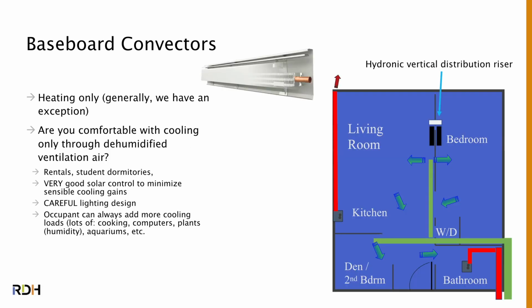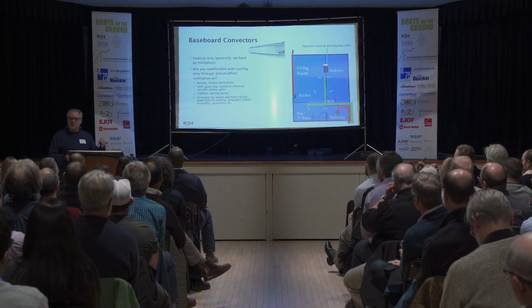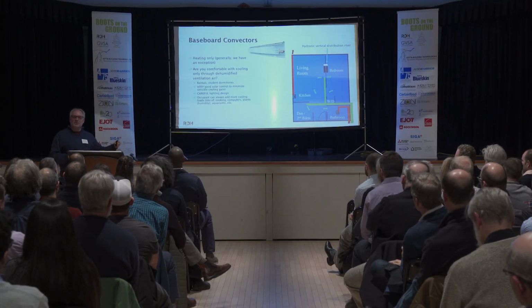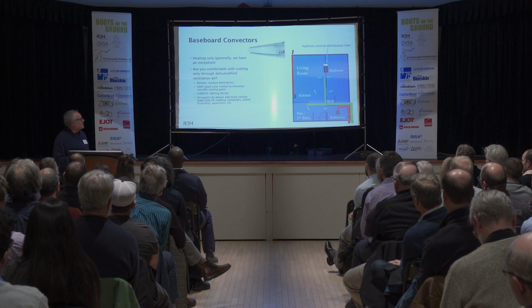But here's the problem, of course: you can provide heating but not cooling, so now you've got to find another way to cool the space. We have done work and studies that say if you're really good at doing your passive control, and you dehumidify the air, you may only experience temperatures as high as 25, 26 Celsius. So they'll be slightly warm, but at least they'll be dry, by dehumidifying the air centrally at your HRV.